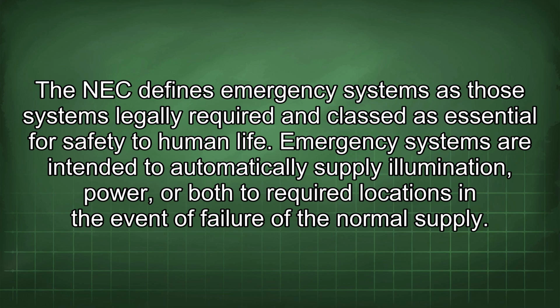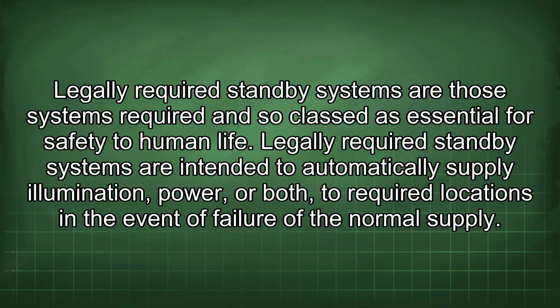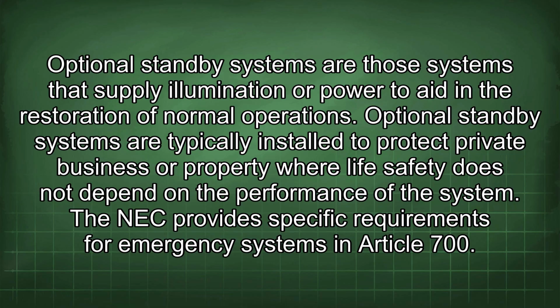the normal supply. Legally required standby systems are those systems required and so classed as essential for safety to human life. Legally required standby systems are intended to automatically supply illumination, power, or both to required locations in the event of failure of the normal supply. Optional standby systems are those systems that supply illumination or power to aid in the restoration of normal operations. Optional standby systems are typically installed to protect private business or property where life safety does not depend on the performance of the system. The NEC provides specific requirements for emergency systems in Article 700.